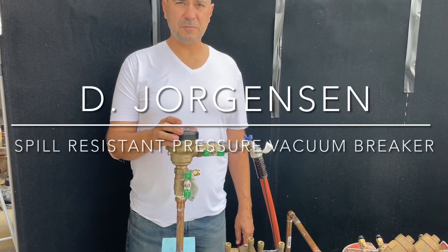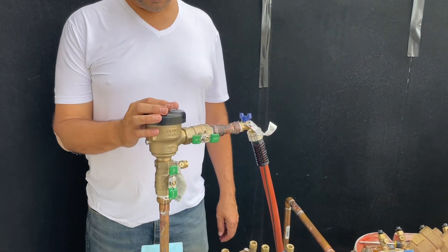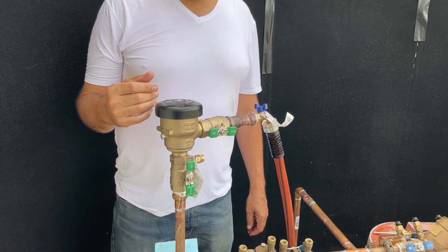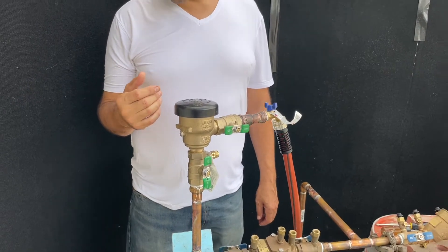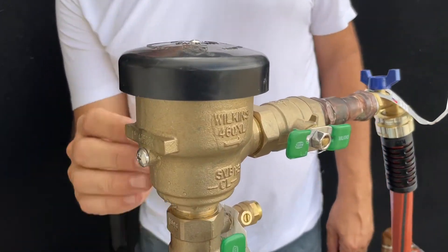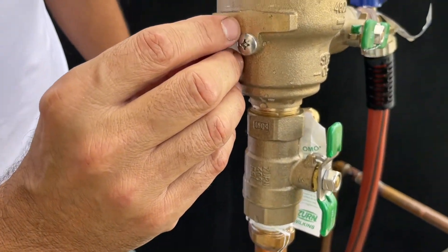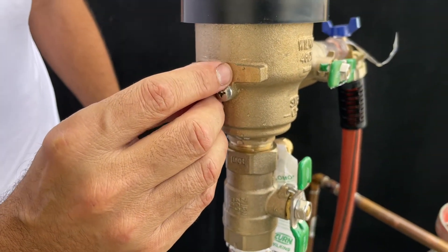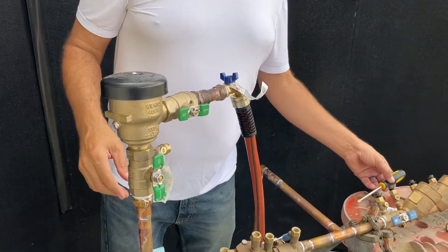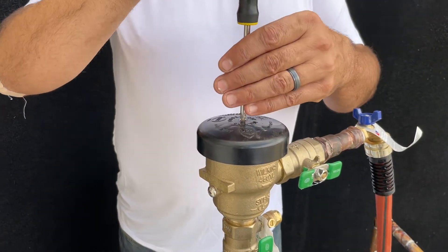Working on the spill-resistant pressure vacuum breaker. We will start by identifying and observing — this looks like a one-inch Wilkins 460XL, serial number 405804. After that is documented, I will proceed by removing the canopy.